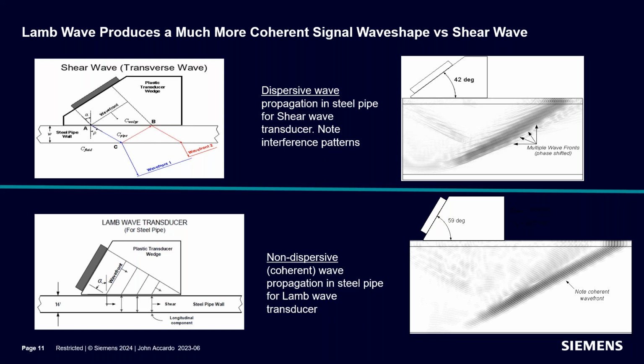With a shear wave, the pipe is an obstacle. It's just something that's in the way that you've got to get a signal through in order to get your flow measurement. And so if you don't resonate the pipe at a frequency that it wants to resonate at, it's not going to produce a very good signal, both in terms of shape or quality and amplitude. So in order to get a signal through it, you've got to hit it harder. Many of our competitors' meters use very, very high voltage transmits, 100, 200, 300 volts in some cases. So you just hit the pipe with a sledgehammer and it makes enough noise to get a signal across the pipe. So it's really how you go about getting the signal into the pipe and getting something that you can work with that is going to be predictable and stable.